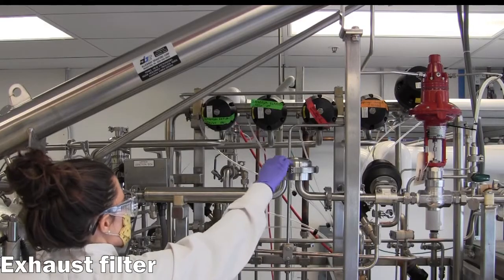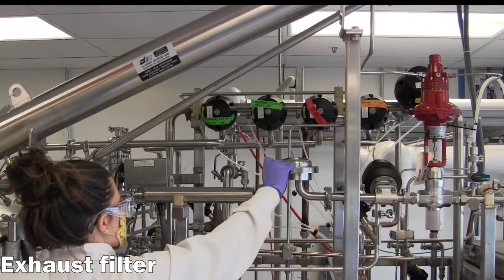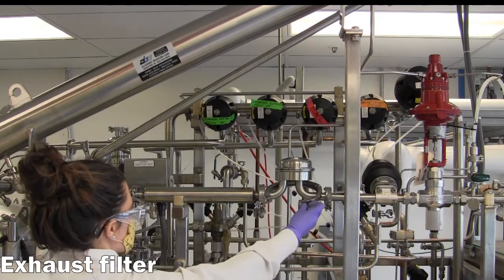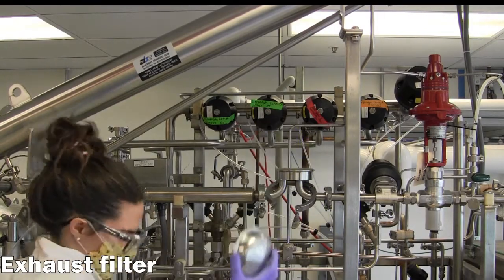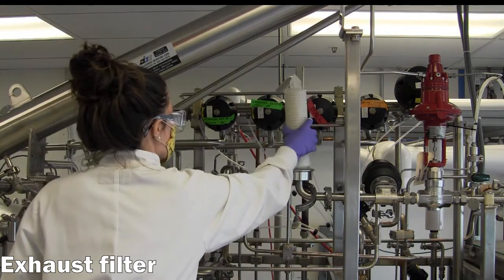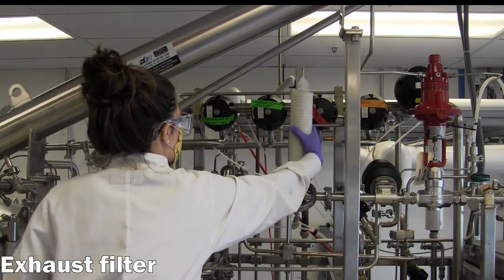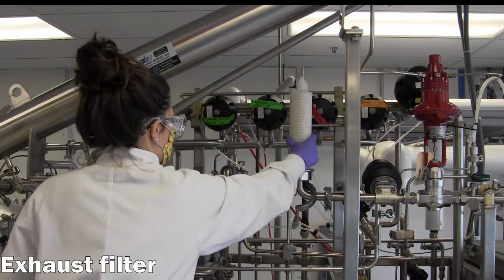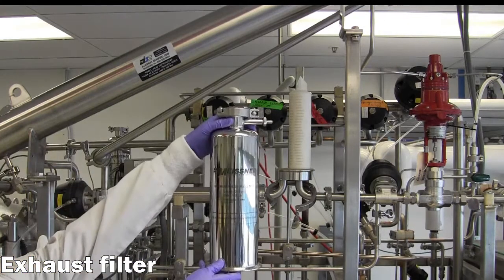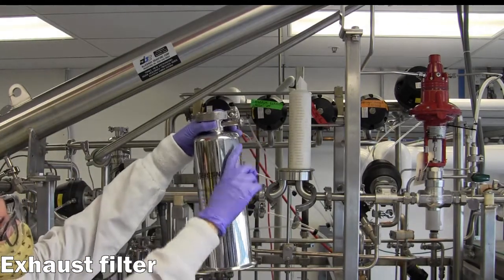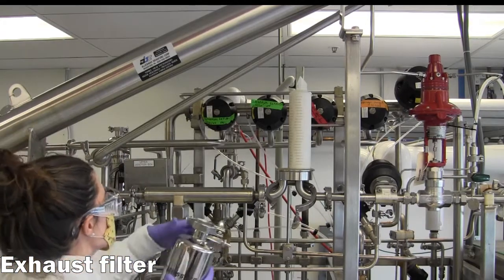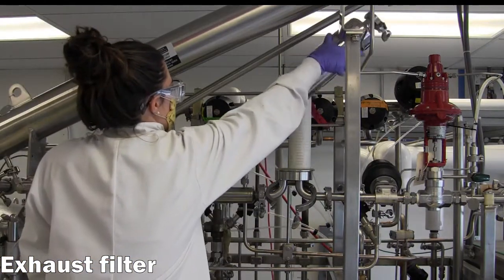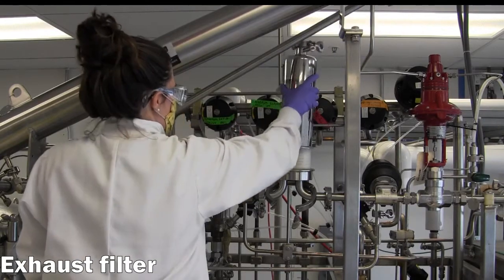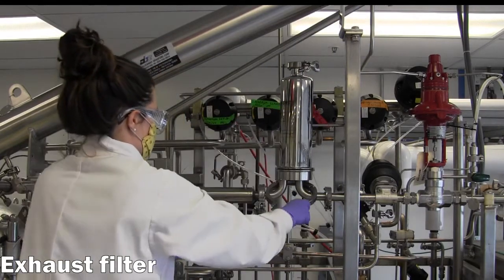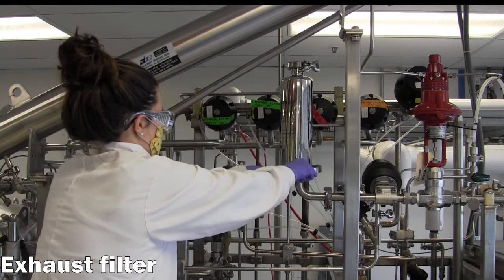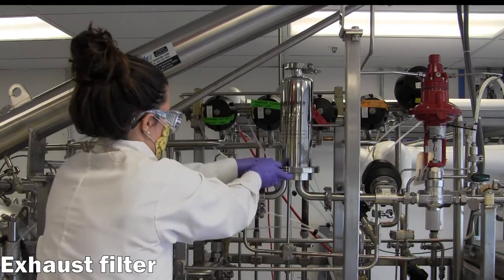This filter filters outgoing air from the reactor to avoid contaminating the lab with any biomaterial. To start, remove the clamp and cap, then screw the filter cartridge in place. Next, secure the housing over the cartridge. It's important that the exhaust housing has a relief valve so back pressure can be released manually in case the filter gets clogged during a foam over event. Replace the tri-clamp and ensure the relief valve is closed.